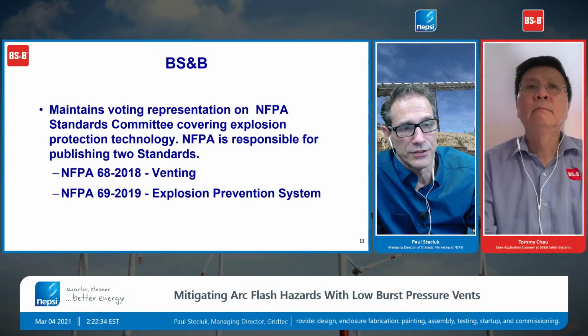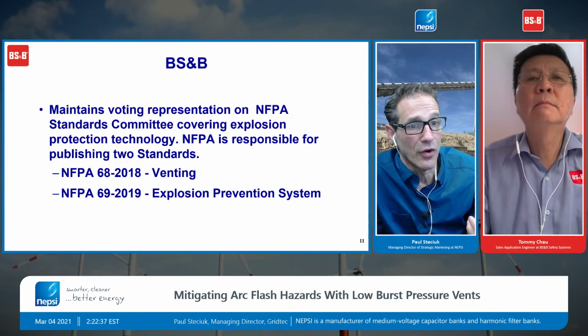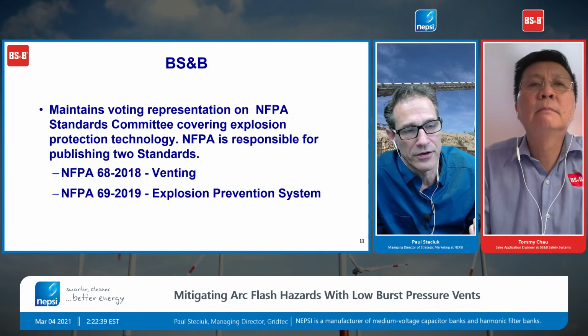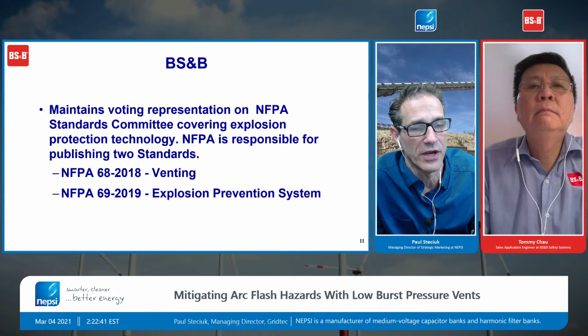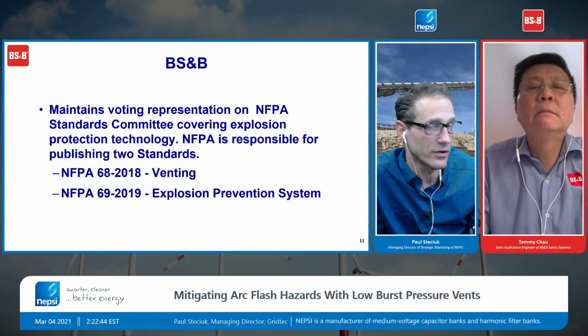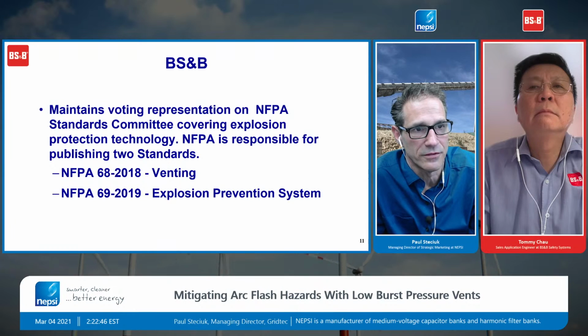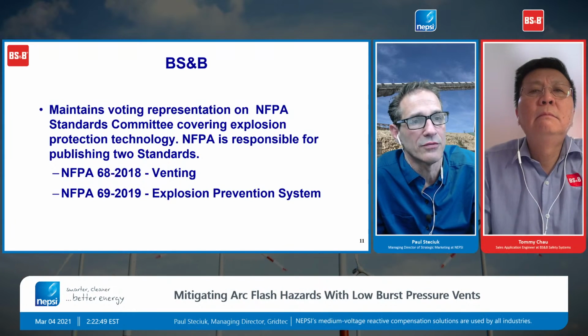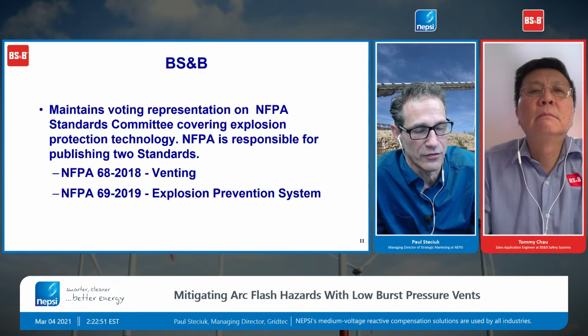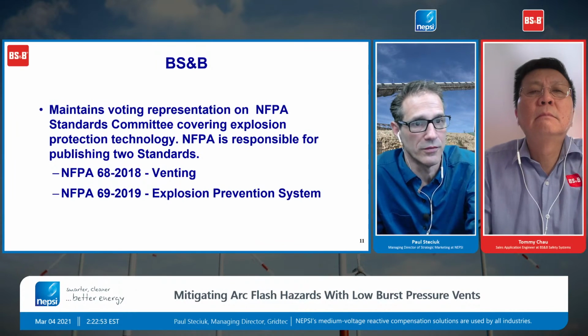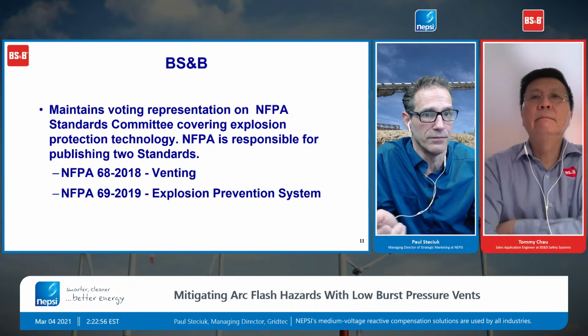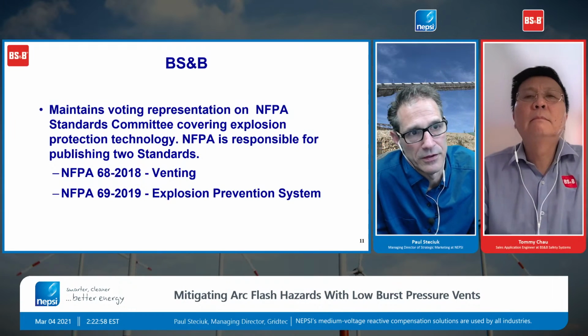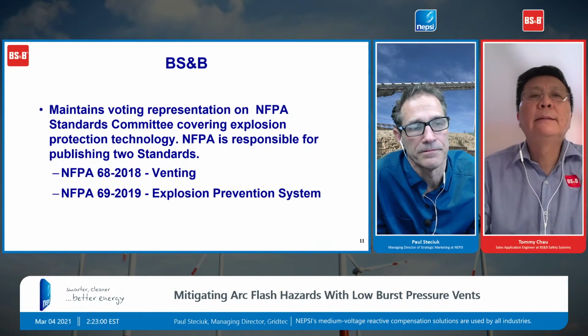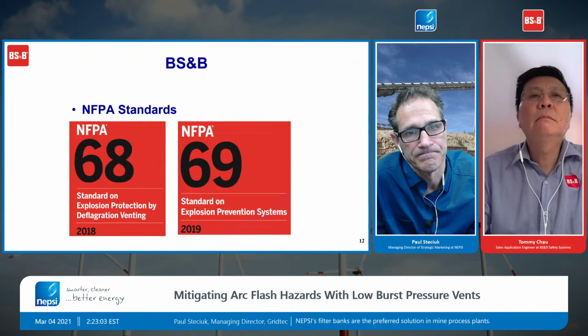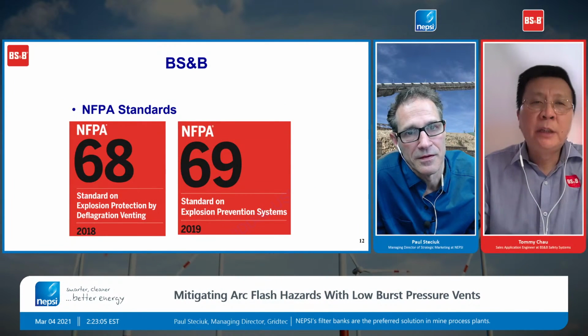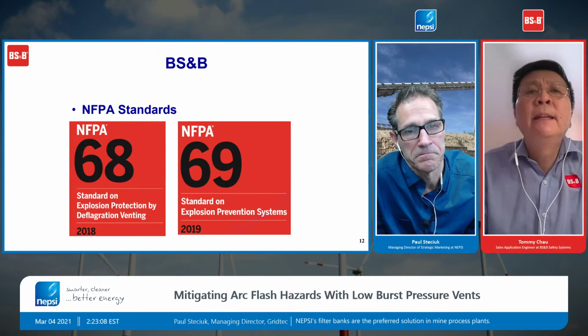And this is one of the things. In one design we showed, we had prefabricated our own vents, but the problem is they're not certified and we don't know what pressure they will actually activate at. So this is a way for us to say, okay, we're not able to send this out to a test lab, but let's do the best we can to make sure that the equipment is designed to prevent those doors from coming off, for instance, or the enclosure being bent up. So that has really been our main use for these. NFPA 68 and NFPA 69.